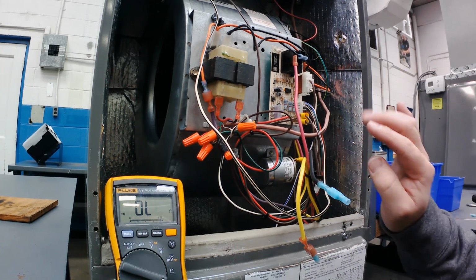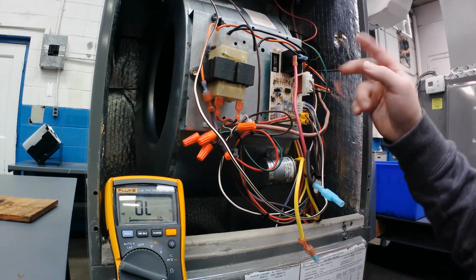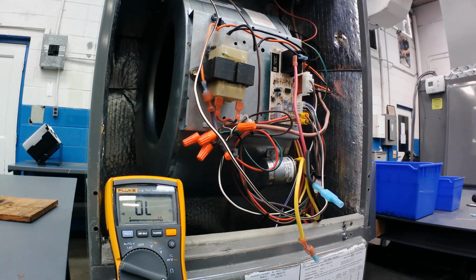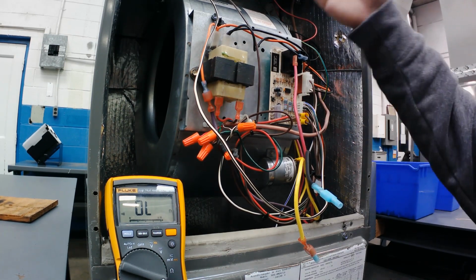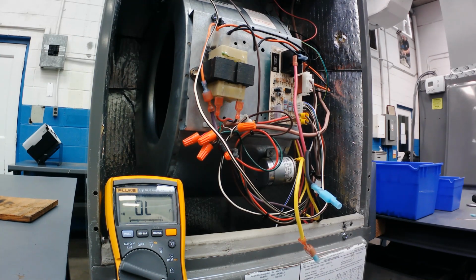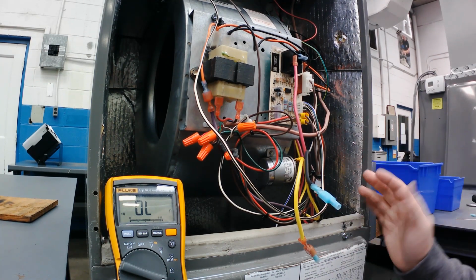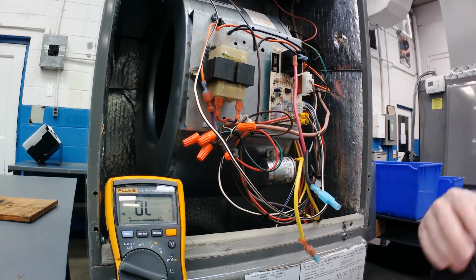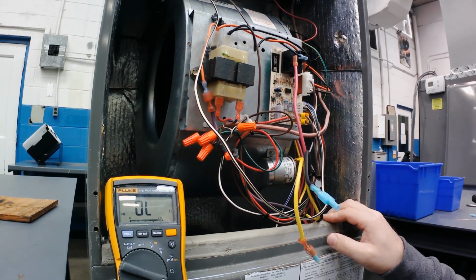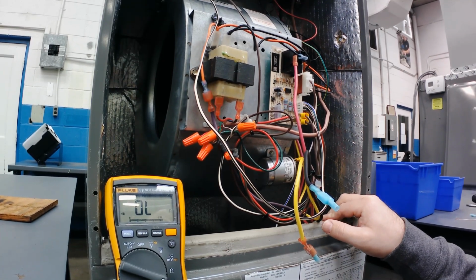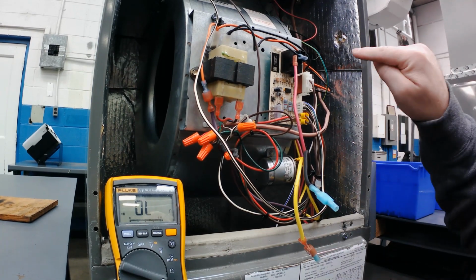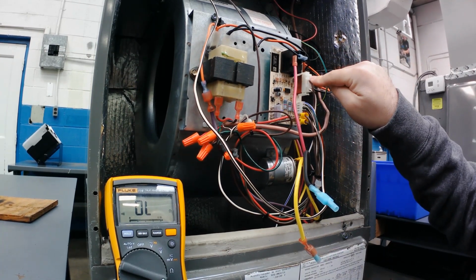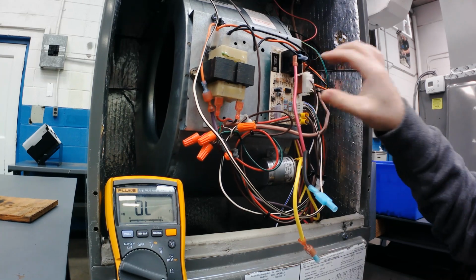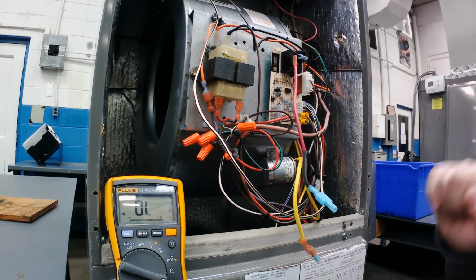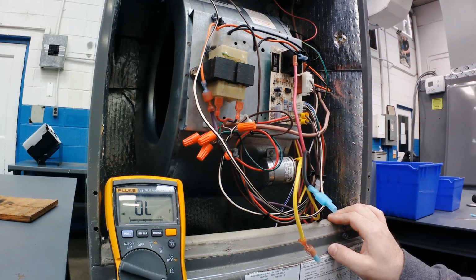Simple voltage checks: power in, power out, the G back to the common for the transformer, W back to common. Of course, if you got 24 volts on W leaving the board, it should go to the heat sequencer. But if I were going to replace this board, I could replace it with a Goodman board. I could replace it with a relay. I'm not going to go into that. I think most people, if you've seen the other videos, whether it's mine or someone else's, probably get the idea of it. But I could put a Goodman board in place of this. Of course, it's not going to plug up right, but as far as wire connections and the thought process behind everything, it would work. All right, I could make it work.